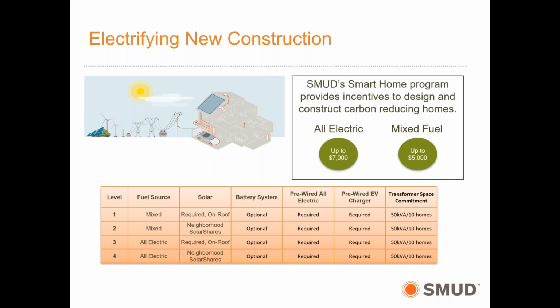Historically, SMUD's been able to accommodate a number of these requests, but as we look ahead to a future with EVs replacing combustion vehicles and electrification of homes in general, the load considerations of local infrastructure have shifted. So sizing the transformer to the number of homes it serves—our standard is a 50 kVA transformer for every 10 homes—gives us the flexibility to electrify communities in the most cost-effective way possible, where DERs can help support the standard design and provide room to upgrade the transformer if needed.